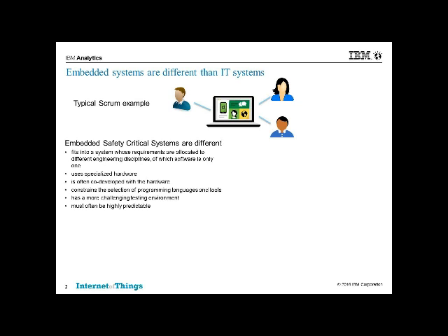Often the systems have to be highly predictable, and you have to be able to guarantee that in all cases the system does the right thing. And IT systems, not so much, right? Part of being predictable is the tight timeliness constraints. For example, on a cardiac pacemaker, if you pace the wrong time, you can kill the patient if you pace what's called the super vulnerable period. In life support devices, you have to respond within certain time frames or bad things happen. You see what's called the fault tolerance time in various conditions, and that can lead to injury or death.